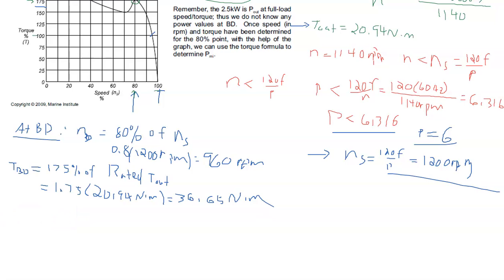Now that we have those, from our torque equation T equals 9.55 times P out over N, the power produced at breakdown will be equal to the speed at breakdown multiplied by the torque at breakdown and divided by our constant, 9.55.